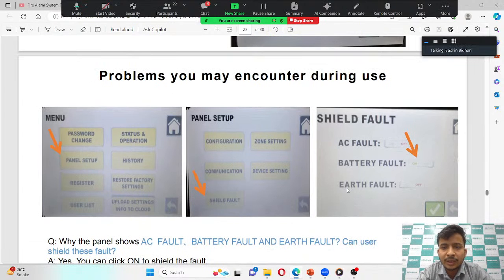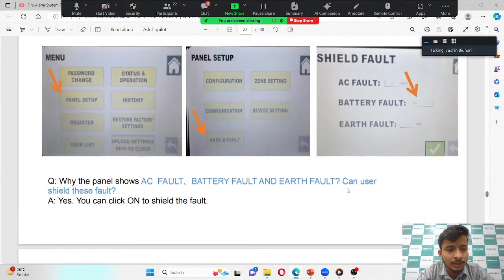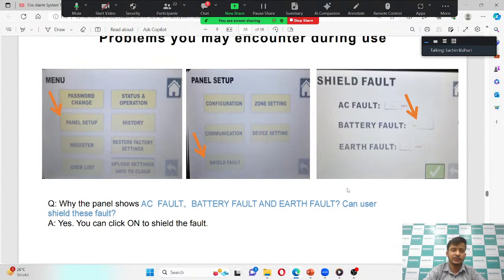Then, problems you may encounter during use. Why does the panel show AC fault, battery fault, and earth fault? Can you shield these faults? Yes, you can click on shield the fault. If the panel gives AC fault, battery fault, and earth fault, and you want to disable or shield that, you just need to go to panel setup, then shield fault. In shield fault you can disable all these three faults if you want, but as per safety norms you need to enable this.